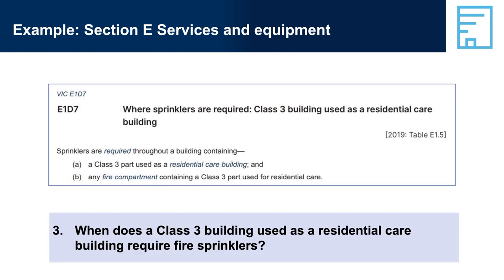Question 3: When does a Class 3 building used as a residential care building require fire sprinklers? A Class 3 building used as a residential care building requires fire sprinklers throughout the building and in any fire compartment that is used for residential care, regardless of the effective height of the building or any other factors. Note: there is a variation to this clause for Victoria.